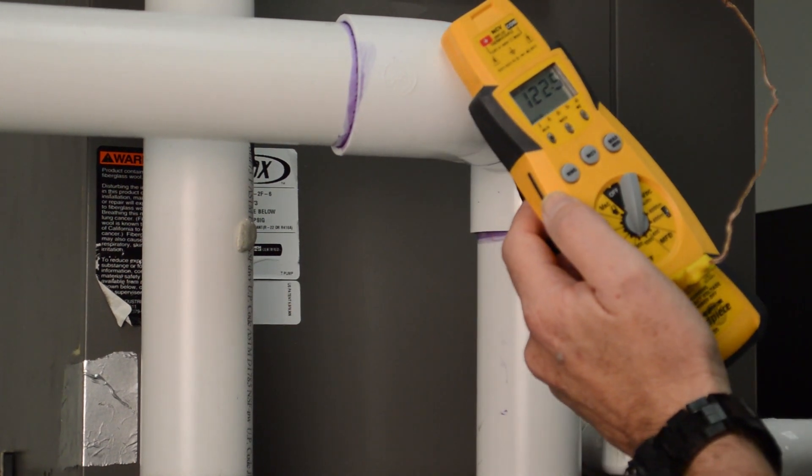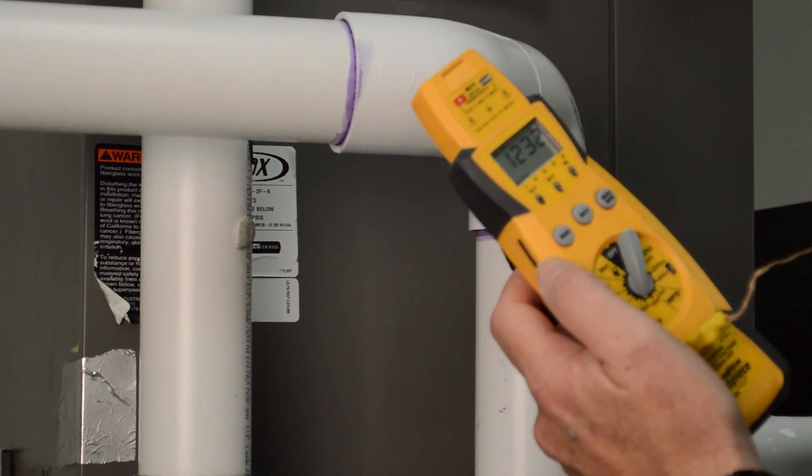The supply side has leveled off at about 122.5 degrees. So we're going to subtract 66.5 from 122.5, and that's going to give us our temperature difference. 66.5 from 122.5 is 56 degrees.